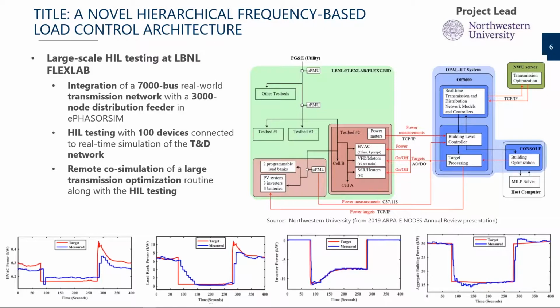We are also running the real-time controllers for both the transmission, distribution, as well as the building level, and co-simulating the optimization for both building and transmission in two separate locations. The transmission optimization was running at Northwestern University in Chicago, whereas this test bed is in California. We exchange data because the transmission optimization needs a certain number of processing cores and processing power, so we co-simulate this together.